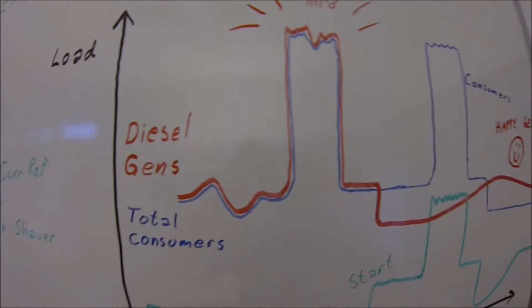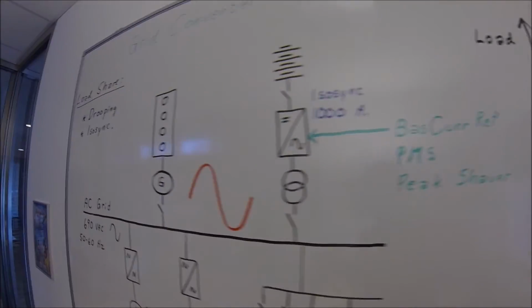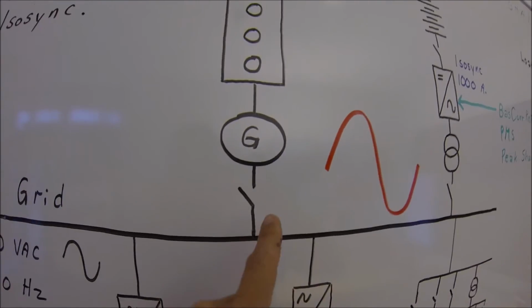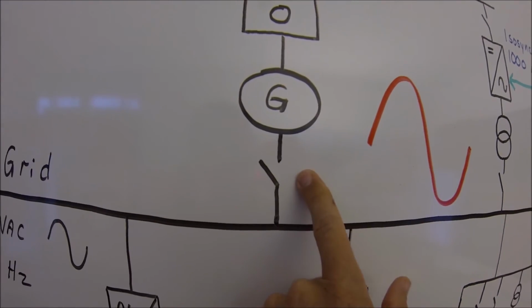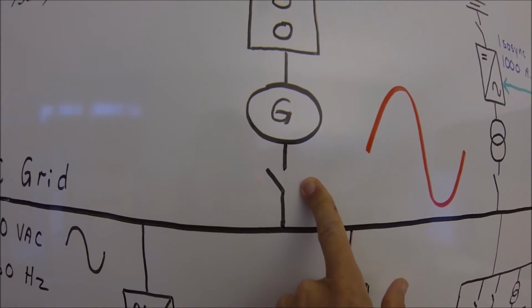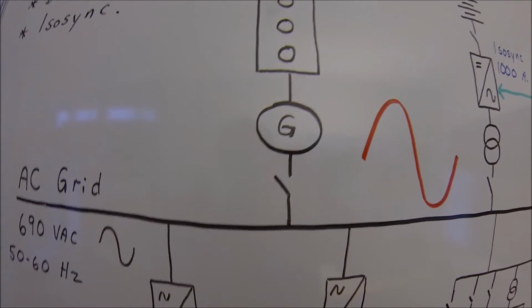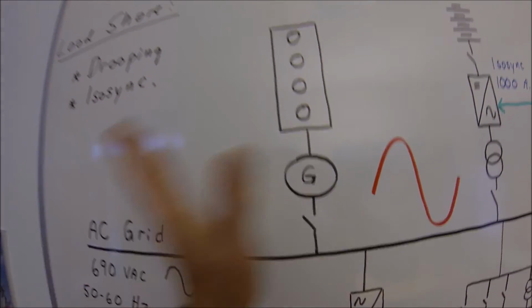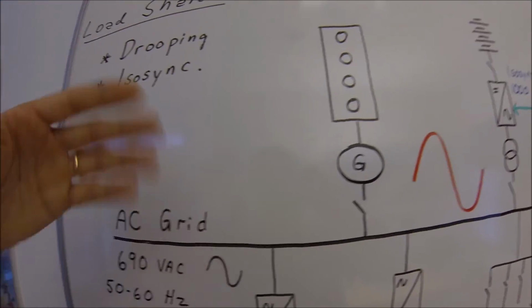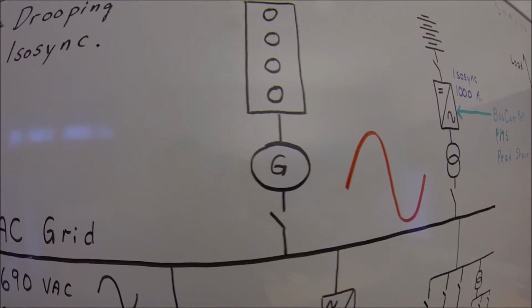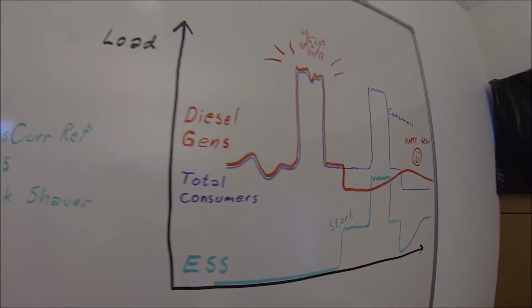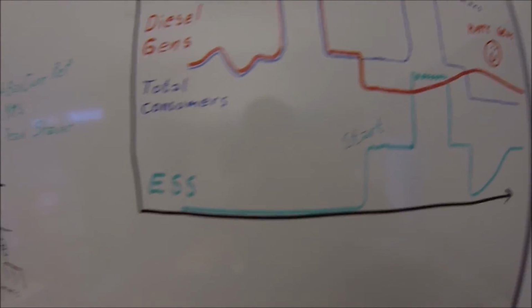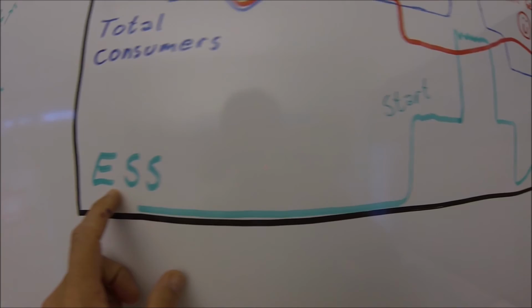You can risk they are lagging with too much load in too short a time. You can risk that the generator protection system will lift off the whole generator. Then you're losing one generator. More load on the other generator, and they also are overloaded, and then boom, boom, boom, you have a blackout on the ship. So the way to do it, energy storage.